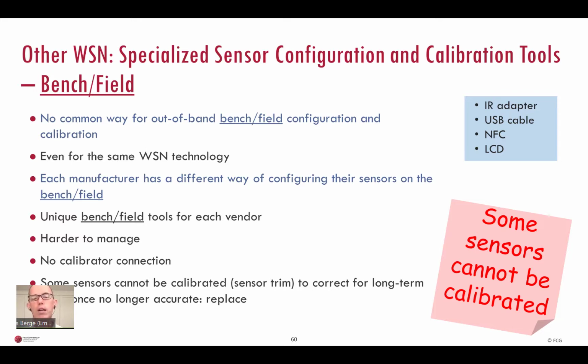One requires a laptop with infrared adapter, another USB cable, a third using NFC, and a fourth from the local operator interface on the sensor. So managing a variety of portable tools in such a heterogeneous environment will cause delays, and the system could even fall into disuse. Direct interface of a portable calibrator is not supported at all, so be careful. Some sensors cannot be calibrated or trimmed to correct for long-term drift. Once no longer accurate, you must throw away and buy a new one.